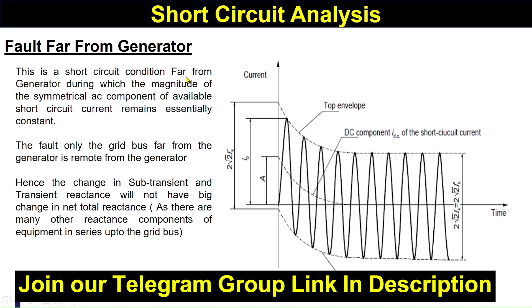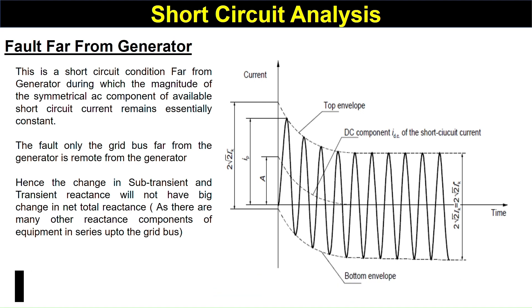Now, for a fault far from the generator — on a bus — the graph is symmetrical. During a short circuit condition far from the generator, the magnitude of the symmetrical AC component of the available short circuit current remains essentially constant. This is because there are many other reacting components in series with the grid, so there is little effect of sub-transient and transient reactance. That is why the graph is symmetrical and the DC component decays very quickly.